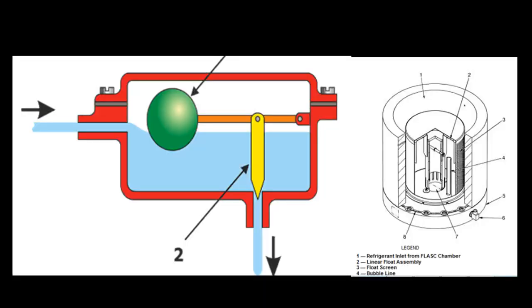The high pressure float expansion valve is used as an expansion device for flooded systems. It is located on the high pressure side of the system and is in open connection to the condenser. It controls the evaporator level indirectly by maintaining a constant level of refrigerant inside the float chamber. The evaporator level depends on the total refrigerant charge and must be adjusted accordingly. If the charge is too great, it leads to excessive flooding of the evaporator; if too small, it leads to starvation.